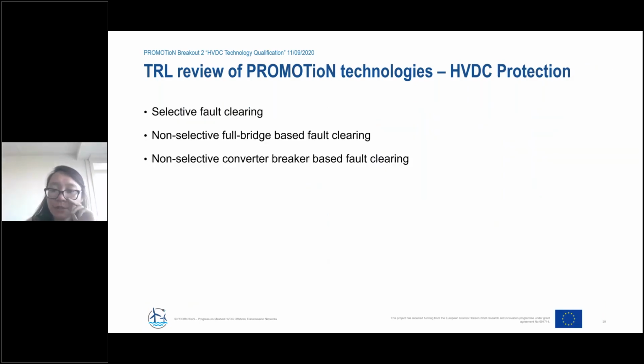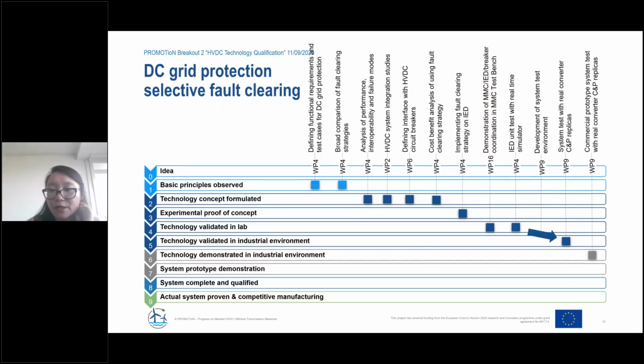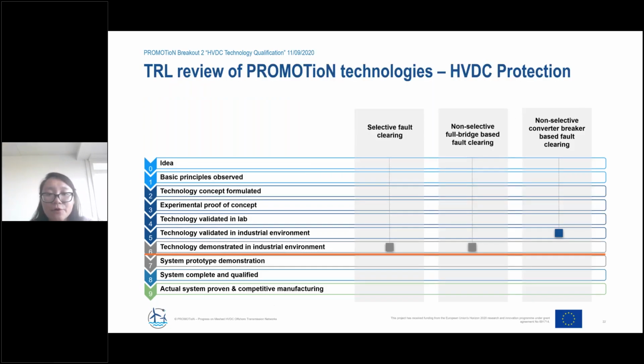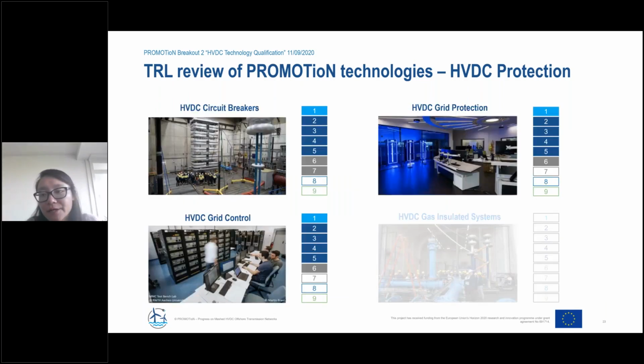For HVDC grid protection, we reviewed selective fault clearing and non-selective fault clearing with two different technologies. For selective fault clearing, by integrating the DC circuit breaker modeling, DC protection development, IED, and converter control and protection replica, the system prototype demonstration advanced the TRL to level 6. The other two non-selective protection technologies acquired TRL 6 and 5 respectively. As a result, the TRL of HVDC grid protection is reviewed as level 6.